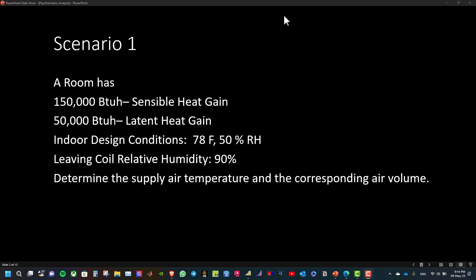In the first scenario, assume we have a room and this room has 150,000 BTU per hour sensible heat gain and 50,000 BTU per hour as latent heat gain. The indoor design conditions are 78 Fahrenheit and 50% relative humidity. The leaving coil relative humidity is 90%. Determine the supply air temperature and the corresponding air volume.